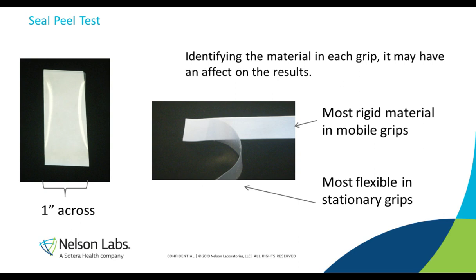So as I mentioned, the seal peel test is regulated by ASTM F88. You use a 1-inch coupon, which is across the seal, not into the package. And it's very important that you identify the materials in each grip because it can have an effect on the results. If you're comparing your results to, say, an independent laboratory or a lab-to-lab facility, and you're finding significant disagreement between the results, take a look at which materials were in which grips.